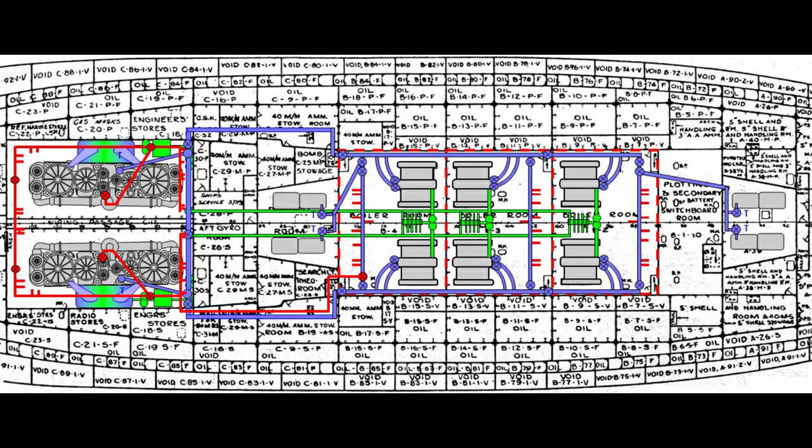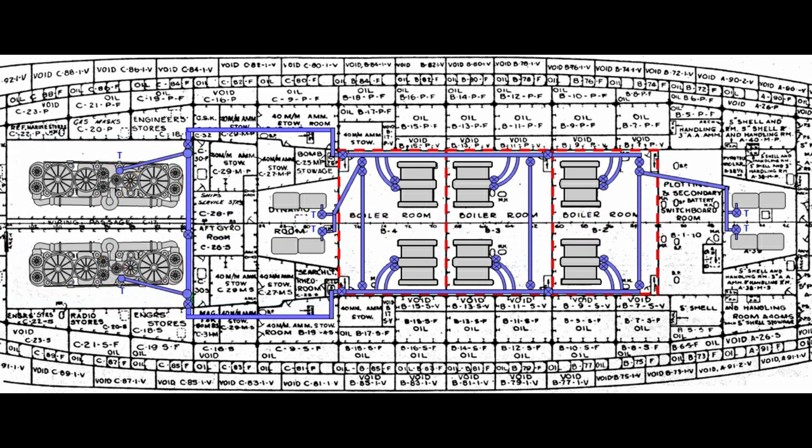Here's a simplified diagram for the steam system that includes three subsystems. The blue indicates the 300-pound steam system that directly powered the ship's engines and dynamos that produced electrical power. The red shows a small portion of the complex auxiliary steam system that powered practically all other devices, including pumps and the steam steering and anchor windlass engines. Finally, we have the green that shows the feed water system that provided water to the boilers. Our focus will be on the 300-pound system for the moment, since it fed everything, including the auxiliary system.